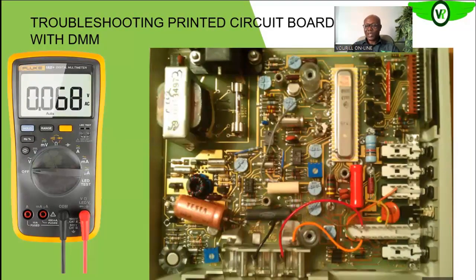So after the voltage has been rectified, you test the rectifier circuit too. Before the rectifier circuit, you have 24 volts AC. Then the output of the rectifier circuit is supposed to be 24 volts DC. If you are not having it, it means that the rectifier circuit is bad.